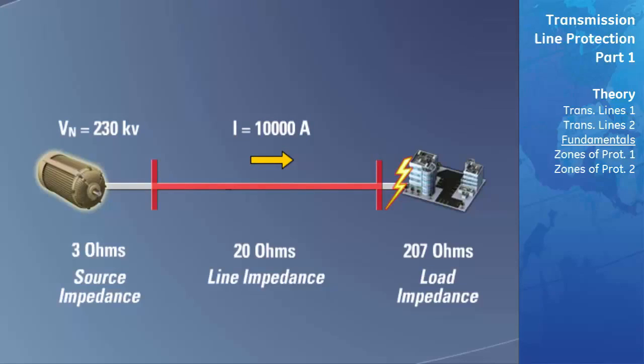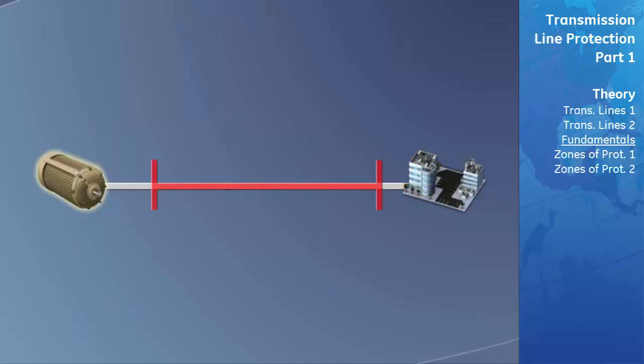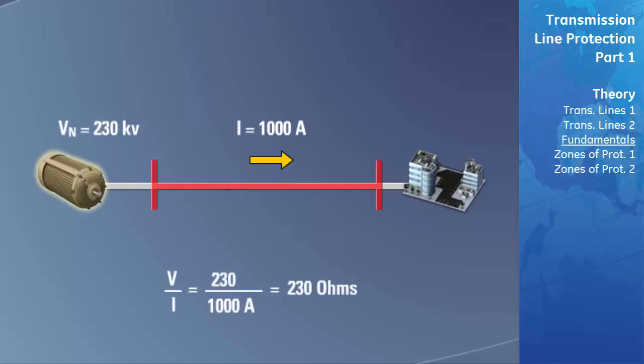Due to the drop in impedance, the current level would now increase substantially. The operating principle of distance protection works in the following way: the magnitude of current and voltage is measured at the beginning of the transmission line, and using these measurements calculates a ratio of voltage over current, which gives you a value equal to the impedance of the total power system. When a fault occurs, thus cutting off the path of current to some of the load, the impedance of the power system will decrease, causing the current to increase and the voltage to decrease slightly.